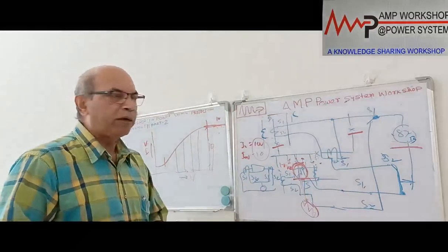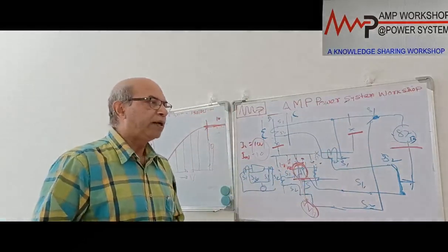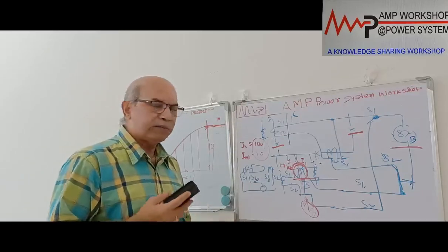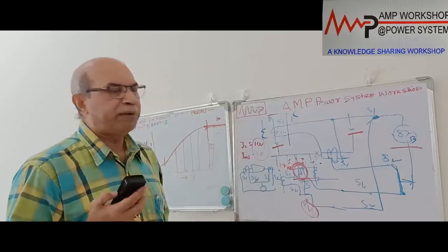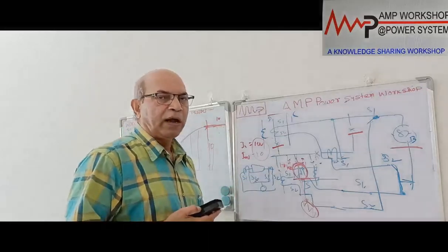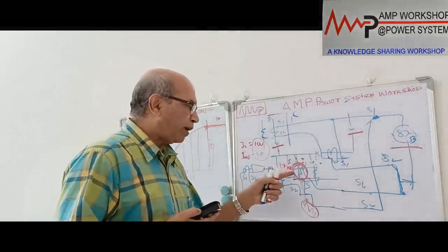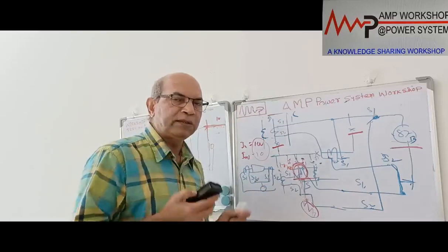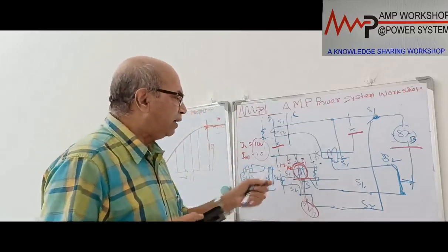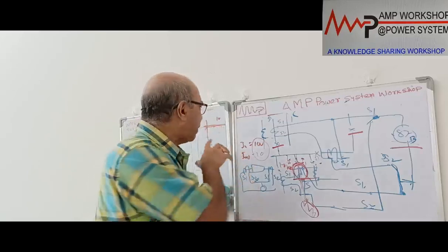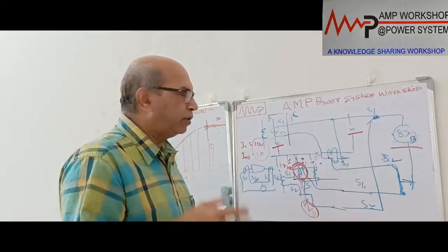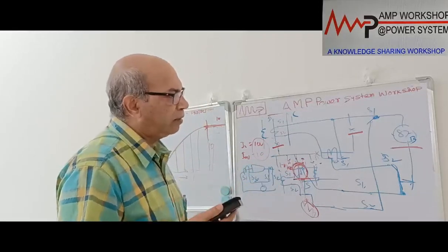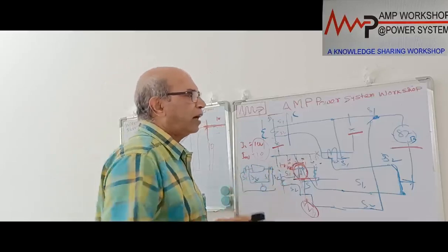So this is one of the problems of this conventional current differential scheme. If it is not very important and the number of feeders is very few, the chance of saturation is very less. If we can select the CT in that way, with the proper burden of the CT selected and the knee point voltage of the CT higher than the required voltage, if the knee point voltage will be 2 times the normal operation zone of the magnetization curve, and if the number of feeders is less, we can use this current differential scheme with some compromise.